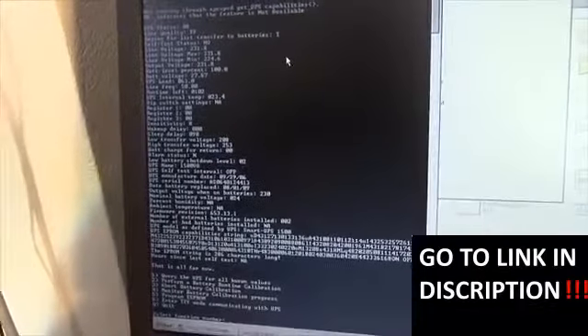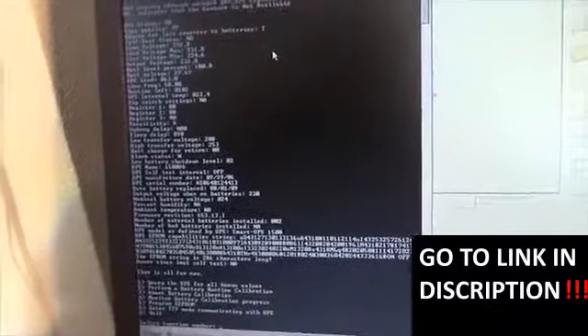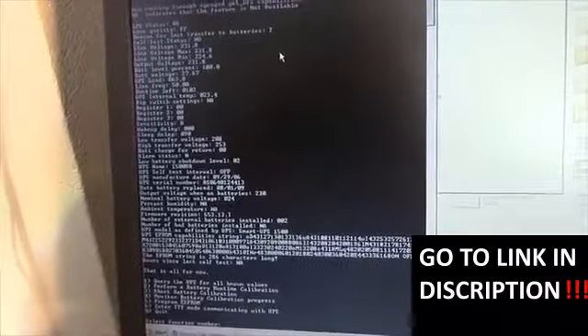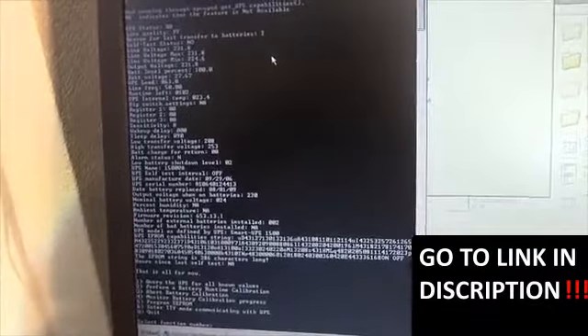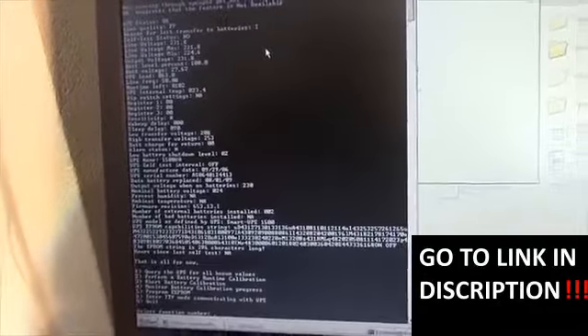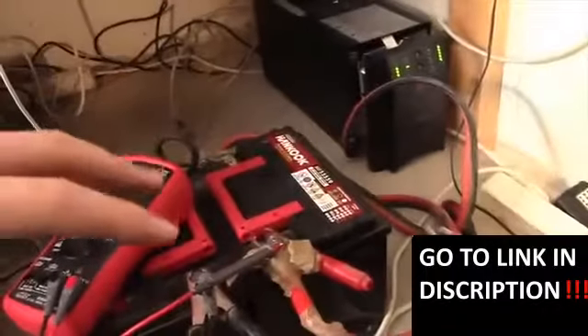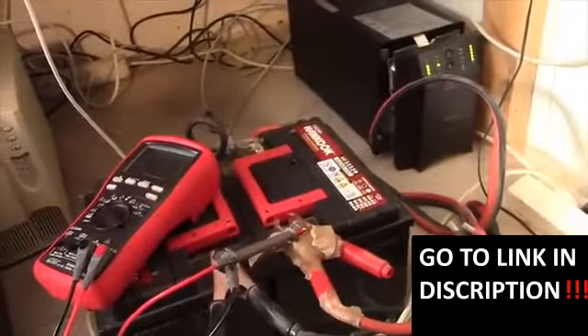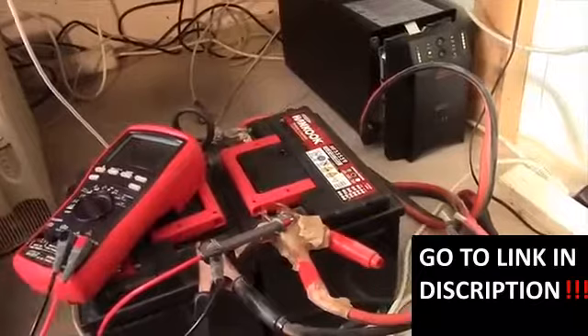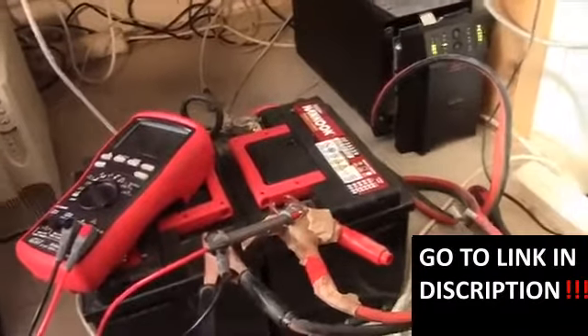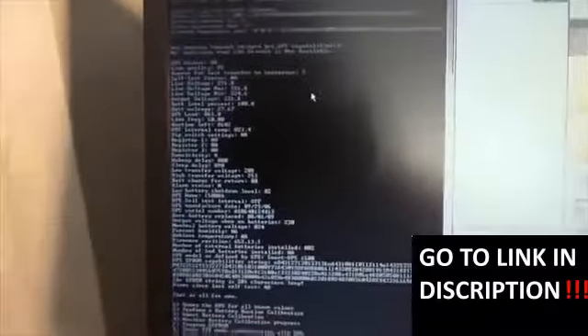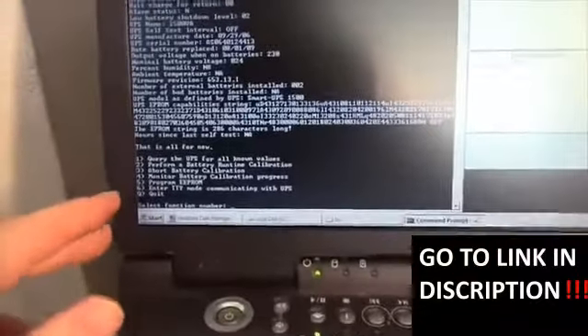Anyway, these UPSs have a function to essentially count with wear leveling, so the battery constant changes with time even if you don't run a battery calibration. So I'm suspecting that this UPS has overcompensated, because I would think that I would get more runtime out of these batteries. So I'm just going to use apctest.exe and run a battery calibration while I'm doing other stuff around the shop.